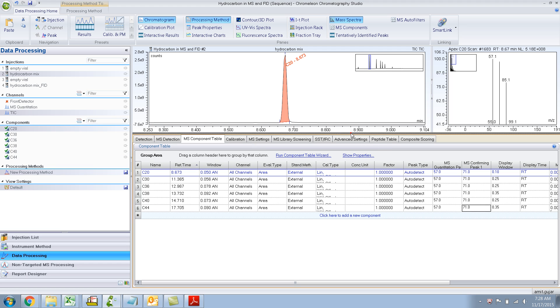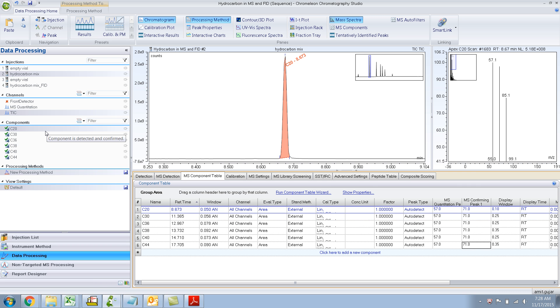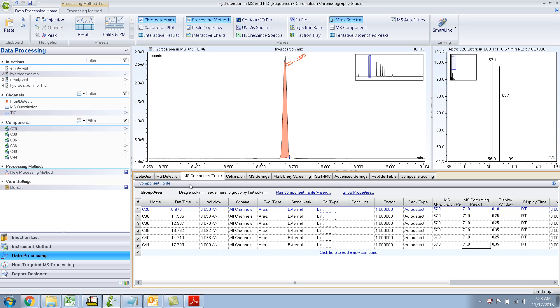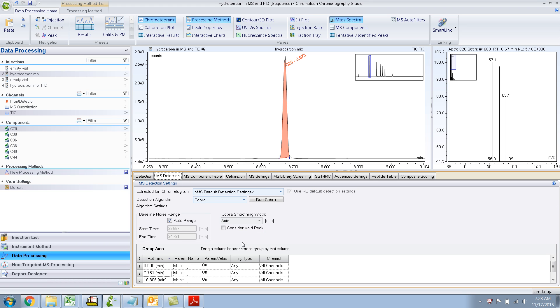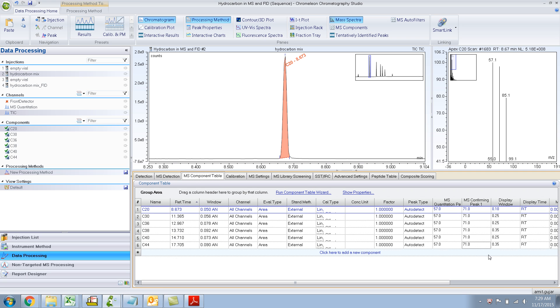Hopefully you've got the concept of components and what to do if you find an exclamation mark. The most common reason is you have not put the confirming peak. Another reason is to check your MS detection settings and make sure you don't have any minimum area set, because if you run the Cobra wizard, sometimes to eliminate very small peaks you put a minimum area - but you have to realize the MS quant ion might fall below that minimum area and that's why it's not detected. A third reason: check your windows to make sure they're wide enough to catch the whole peak.